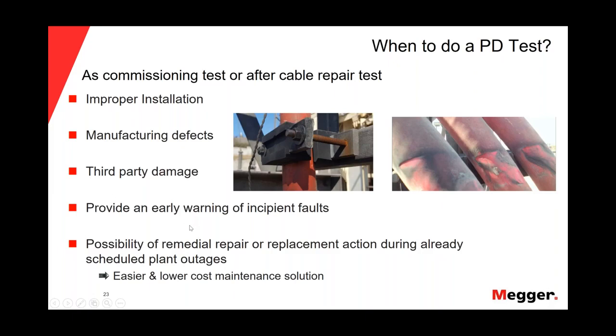So the partial discharge will provide an early warning of incipient faults, and we will have the possibility of remedial, repair, or replacement action during an already scheduled planned outage.